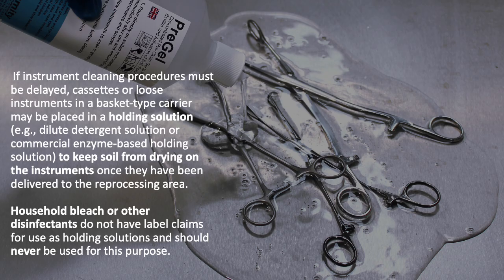When we take the instruments to the reprocessing area and there is a delay in the cleaning for any reason, we must place the instruments in a holding solution. This holding solution will keep the soil from drying on the instruments. Examples of holding solutions are dilute detergent solution or commercial enzyme-based holding solution. We cannot use household bleach or other disinfectants that don't have label claims for use as a holding solution, and we should never use them for that purpose.